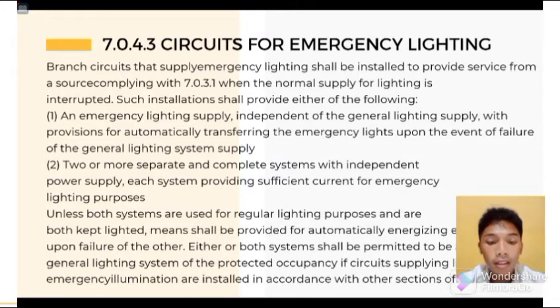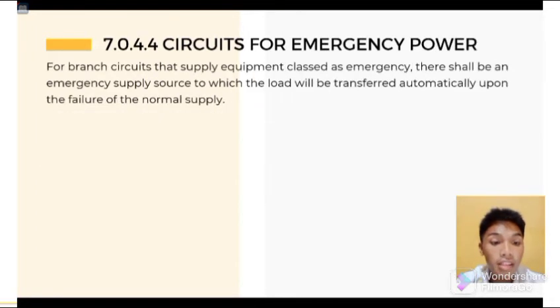Okay, so let's now move on with the circuits for emergency power. For branch circuits that supply equipment classified as emergency, there shall be an emergency supply source to which the load will be transferred automatically upon the failure of the normal supply. Okay, so that will be the last for these sources of power.